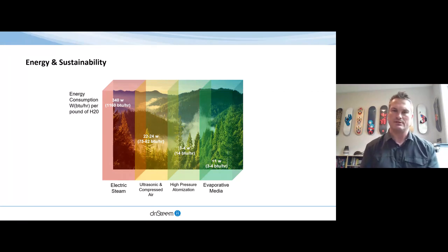Evaporative media is the most energy efficient of these methods, typically using less than a watt of energy per pound of moisture evaporated in the airstream. Everything has a benefit and an adverse. With evaporative media, the benefit is the high energy efficiency and the cooling effect that can be gained. The downside is that it can be very difficult to control our plus or minus output with an evaporative media system. So those are just some things to bear in mind. If we're using evaporative media to sustain a baseline range within a building and then applying a secondary system in a more localized environment, that may be a more energy efficient way to approach the project.